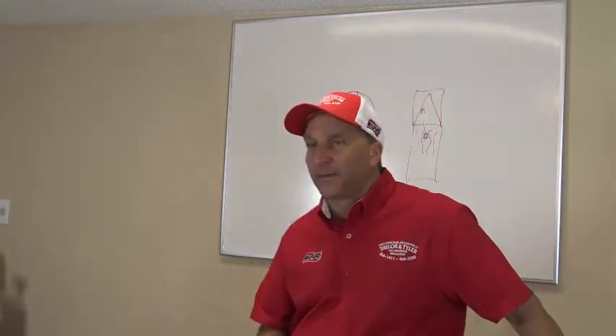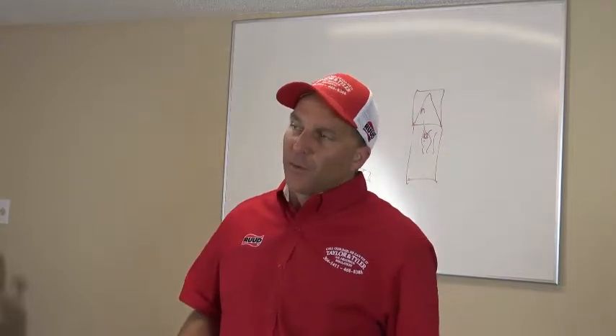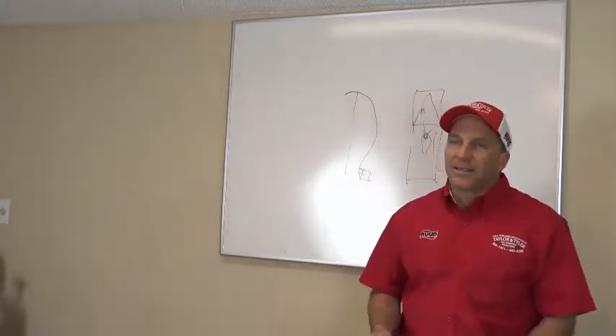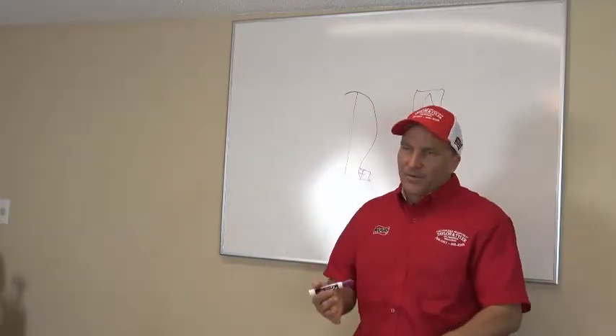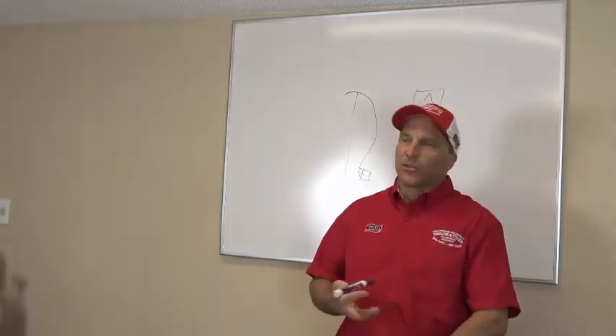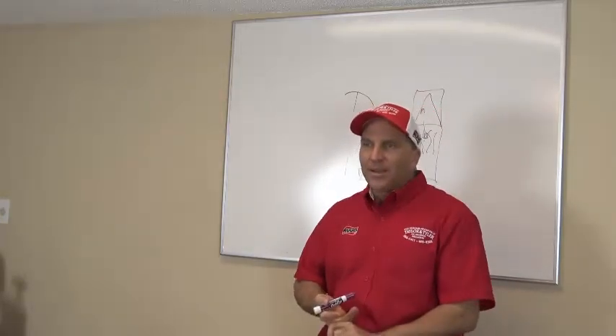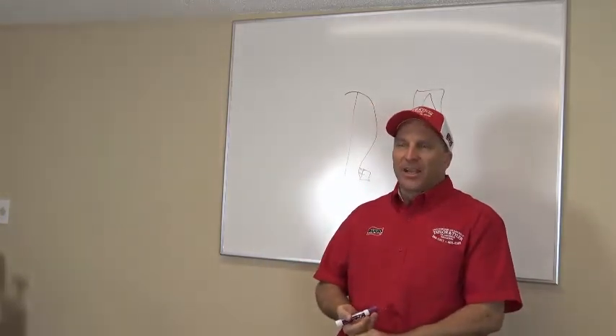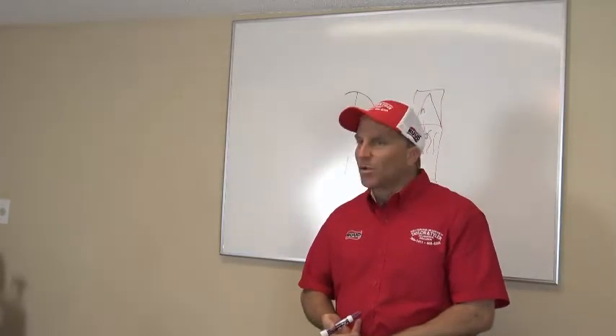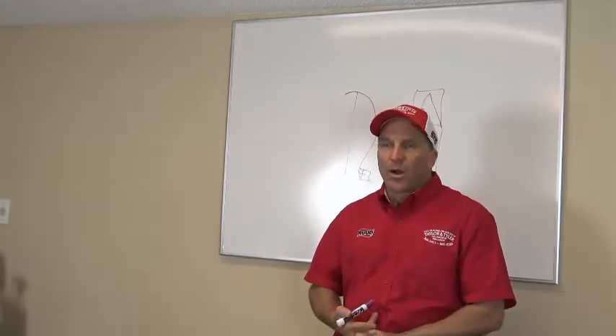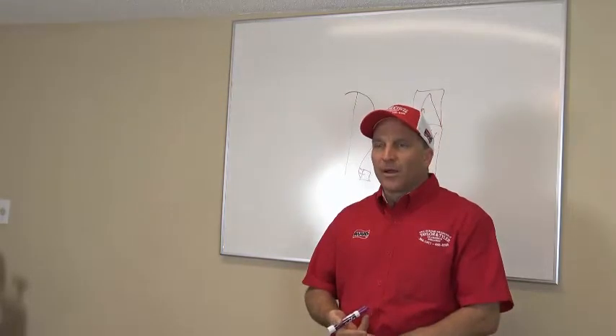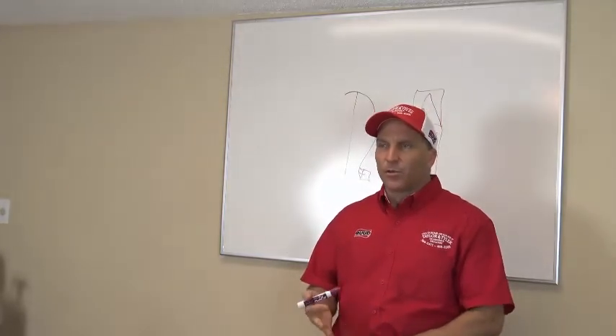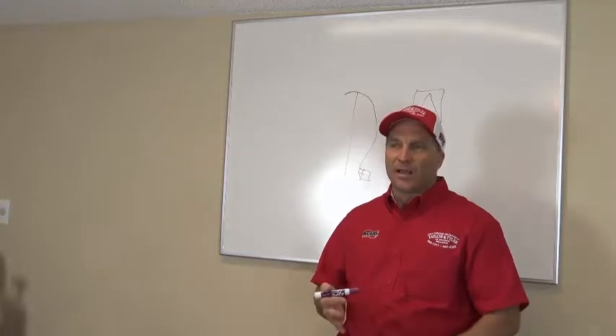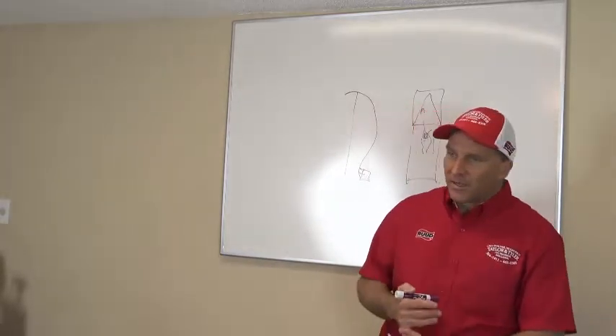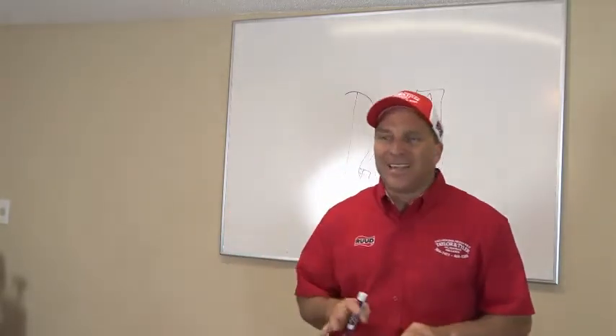Now, how are you going to know that? Head pressure, suction pressure, superheat, subcooling, right? That's going to tell me whether you got the proper TXV, whether your piston's the right size, whether it's restricted, whether it's open, wide open. You got to understand what your head pressure, suction pressure, superheat, and subcooling mean. If you do not know what all that stuff means, go to the other tapes that we have that explain low superheat, high subcooling, high head pressure, low head pressure, low this, high that. It explains all that. We have other tapes that go through in detail about that.